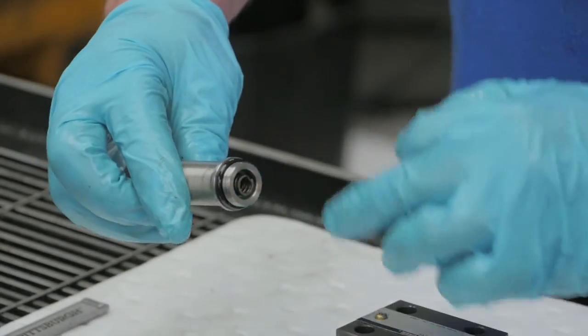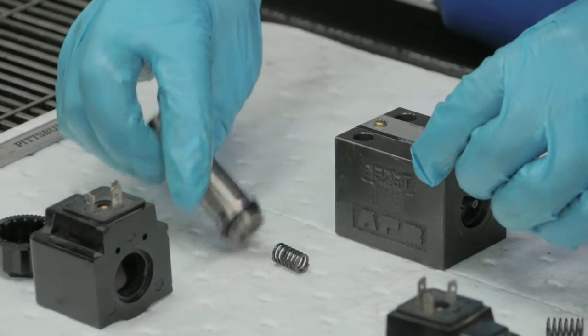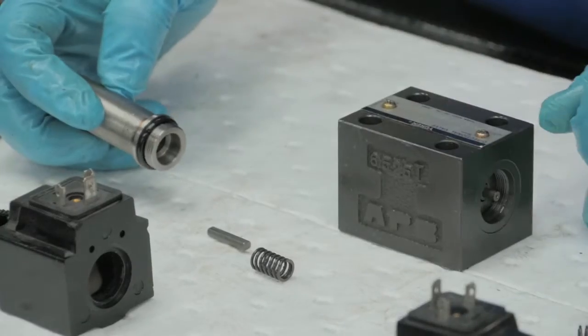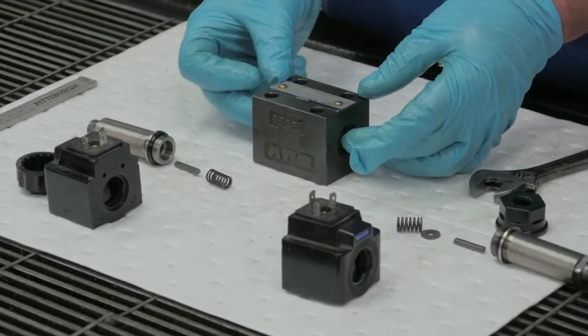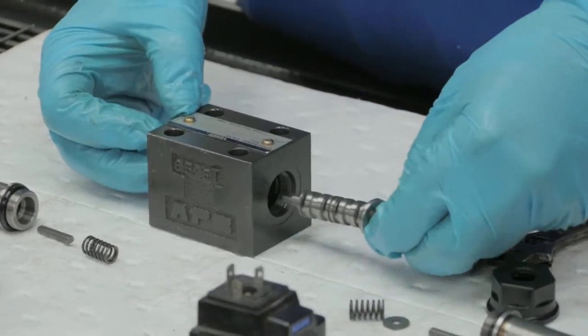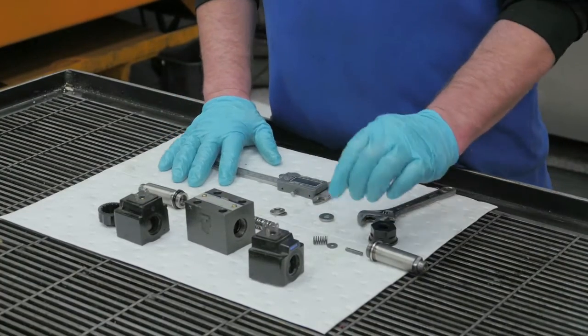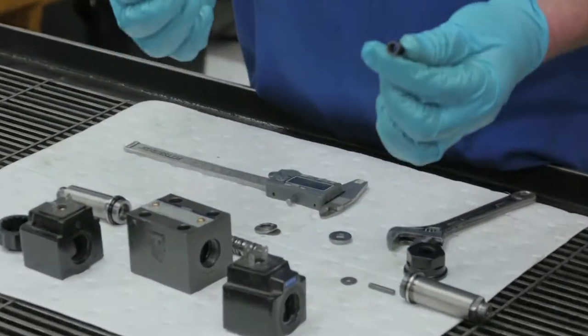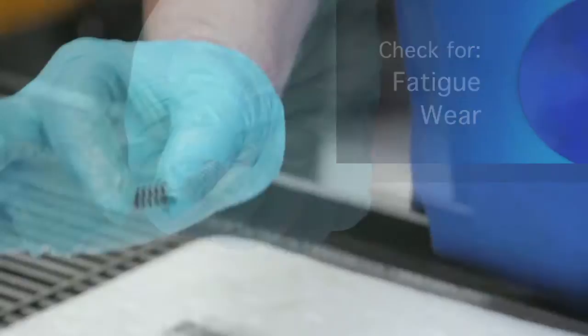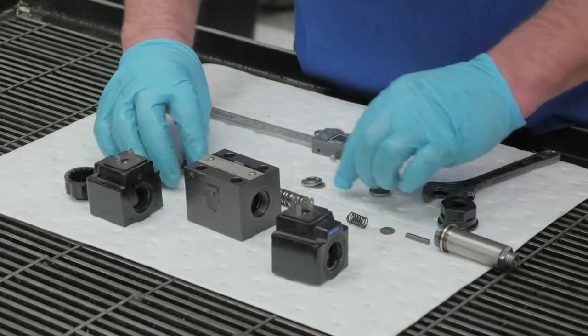This is a tube, O-ring, spring, and slide hex key. Now I'll take the spool out of the directional valve. Next, we're going to check for fatigue and wear on our springs. No wear on the springs, no fatigue — springs look good.